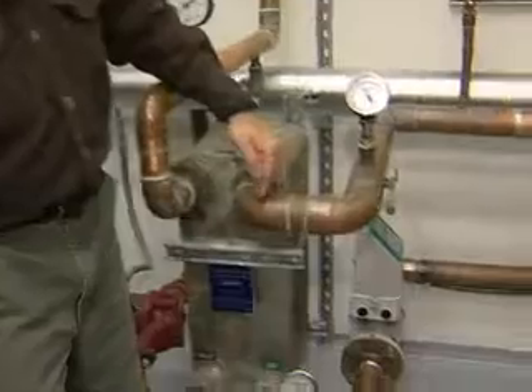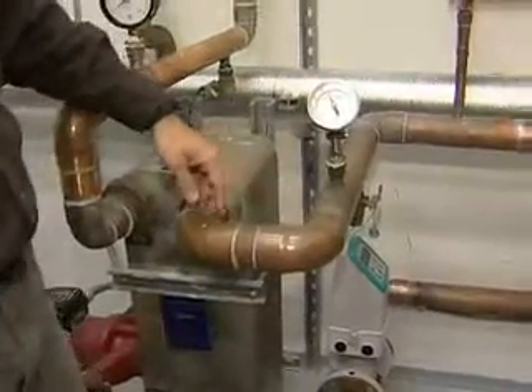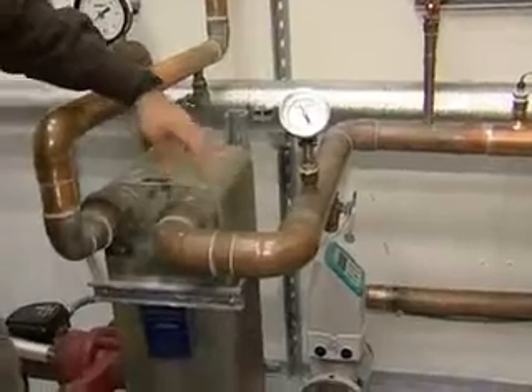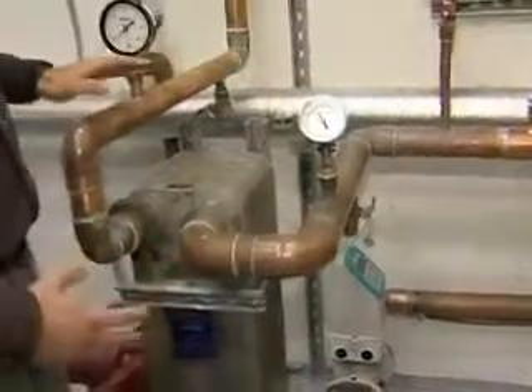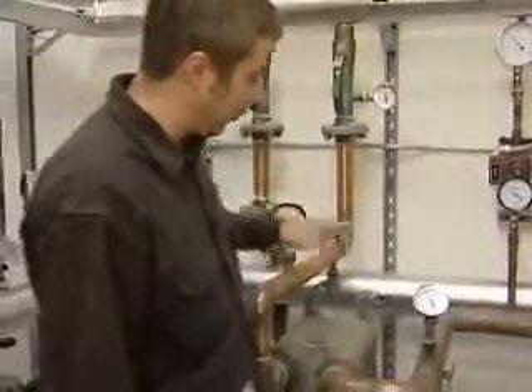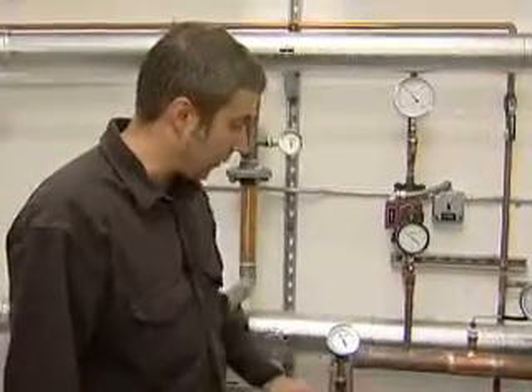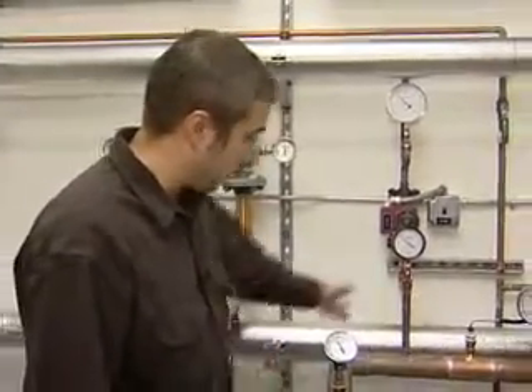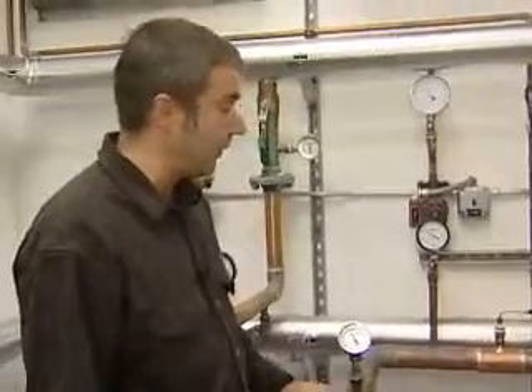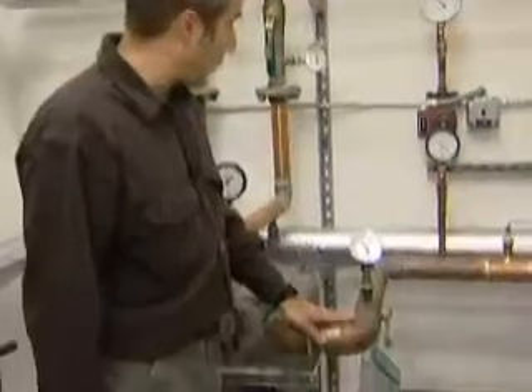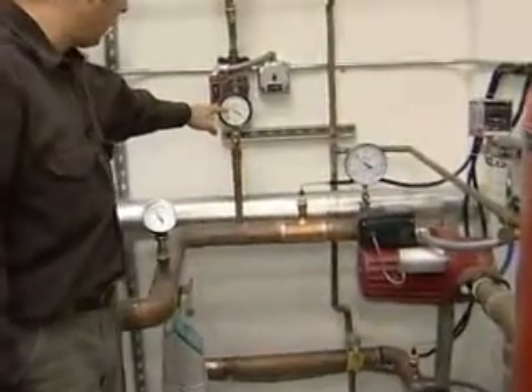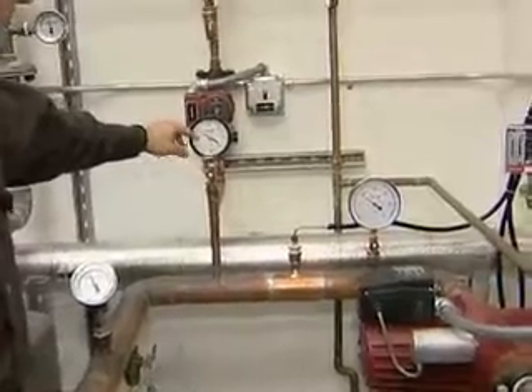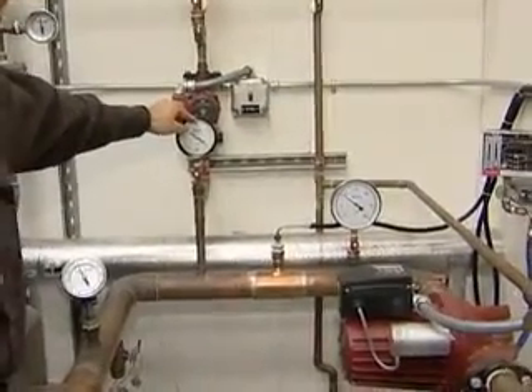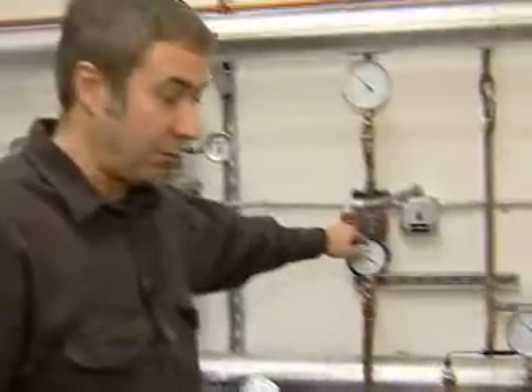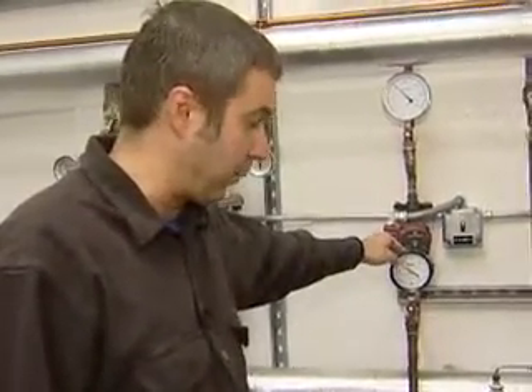Now on the secondary side of the heat exchanger, this is the loop that goes out to the remote building. And again, we should see temperatures that are slightly lower than the engine coolant. So if the engine coolant was coming in at 190, we might see our hot glycol coming out of this side at say 185 or 180 degrees. And then it circulates, runs out of the building over to an adjacent building. Because it's a longer piping loop, we run it at a higher pressure. So this system right now, because it's cool, is only running around 20 psi. Under normal operating conditions, we should see it up closer to about 30 psi. It has a 50 psi pressure relief on it that would, if you over temperature the system, would blow off.